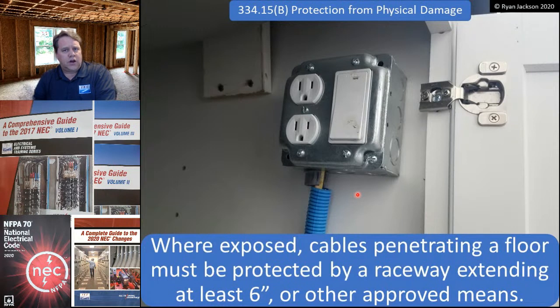Now, a lot of people get hung up on the issue of physical damage. Can you use electrical nonmetallic tubing, ENT, where it's subject to physical damage? No. So are we looking at a violation here? Well, you put the NM cable in a pipe because the NM cable is exposed to physical damage, but you used a pipe that can't be subject to physical damage. Well, wait a minute now. Subject to physical damage is not just a function of the location, it's a function of the wiring method. What's likely to physically damage NM cable might not necessarily damage ENT, and what might damage ENT may or may not damage flexible metal conduit.